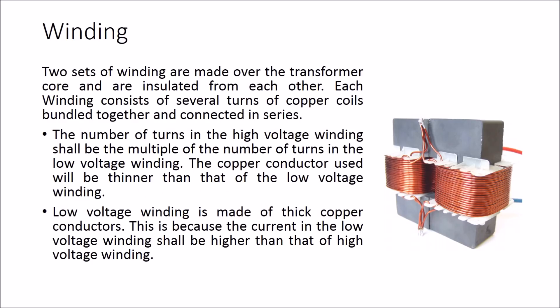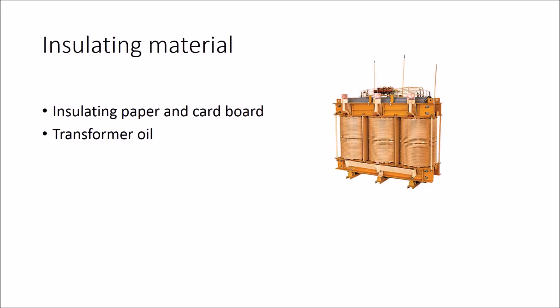Two sets of windings are made over the transformer core and are insulated from each other. Each winding consists of several turns of copper coils bundled together and connected in series. The number of turns in the high voltage winding shall be a multiple of the number of turns in the low voltage winding. The copper conductor used in the high voltage winding will be thinner than that of the low voltage winding, which is made of thick copper conductors because the current in the low voltage winding is higher. Insulating paper and cardboard are used in transformers to isolate the primary and secondary windings from each other and from the transformer core.